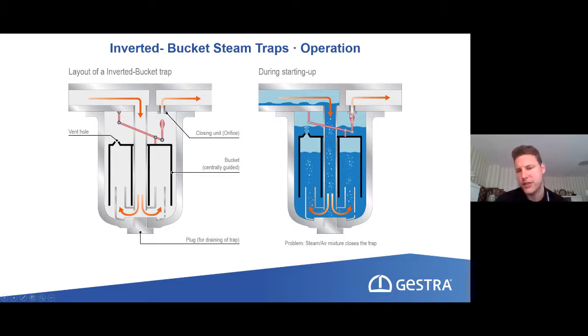But here you see the first disadvantage. If we have a closing here in this steam area, it's much harder to make it close tight so that it doesn't have any steam losses. It's much easier to shut a steam trap when it's in the water area rather than in the steam area.